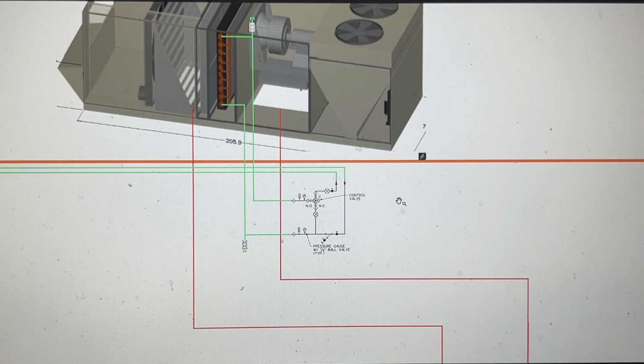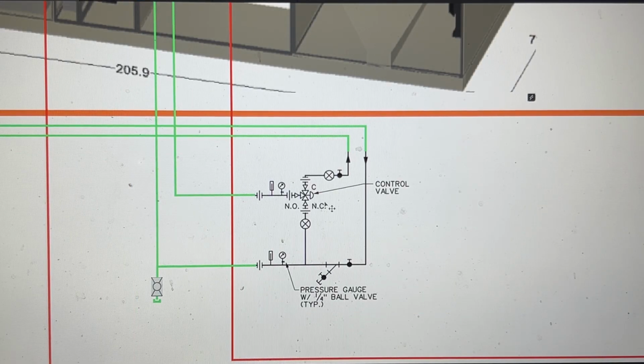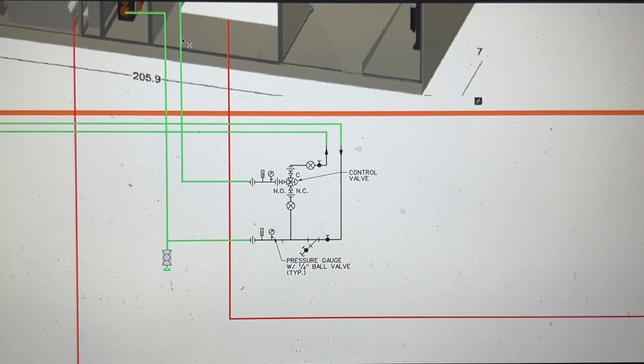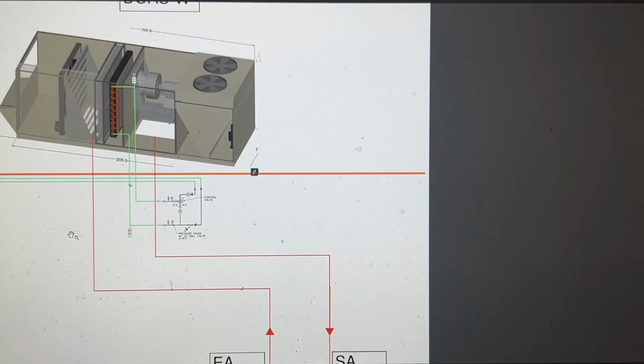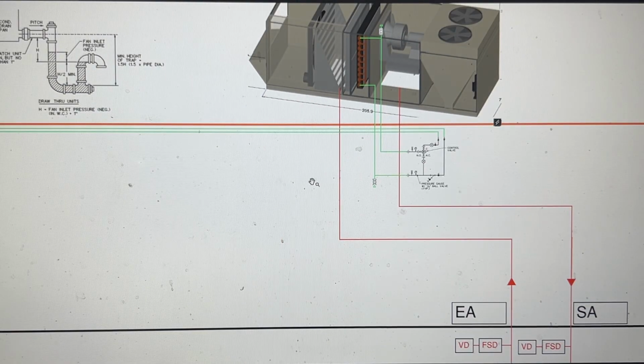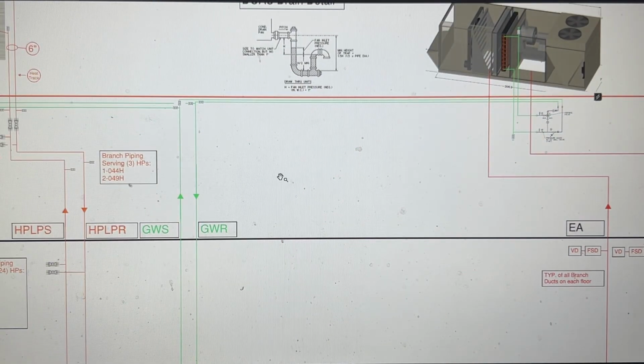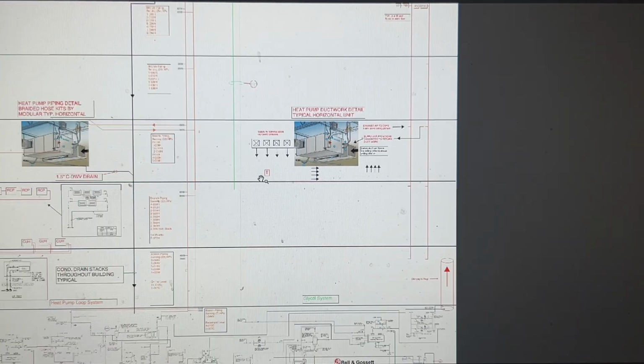So as a part of making the schematic, I pull stuff from the submittal. I pull details from the back of the contract drawings. I kind of take different bites from different sections of the project and try to incorporate it into one as required. So, for instance, this one comes with a 3-way control valve. So they want to keep the glycol moving even if there isn't demand for it up at that unit. This valve will close, and the supply will return back to the mechanical room if heat isn't required up at the unit. So let me cruise down here to the mechanical room.